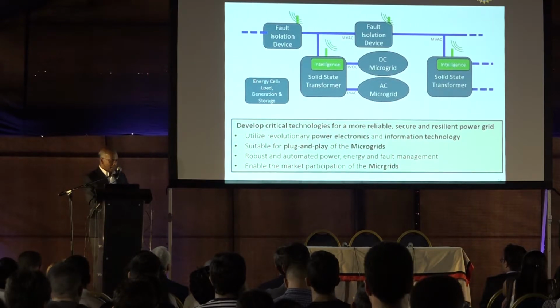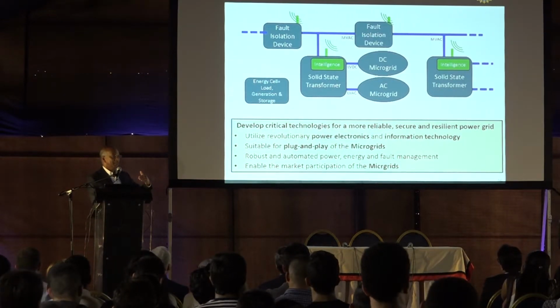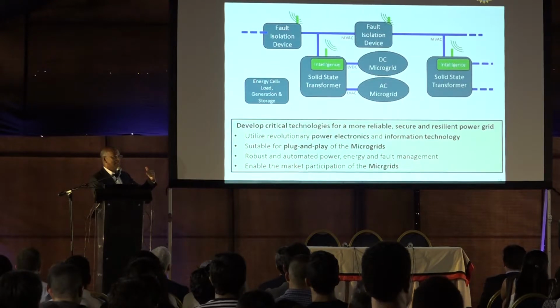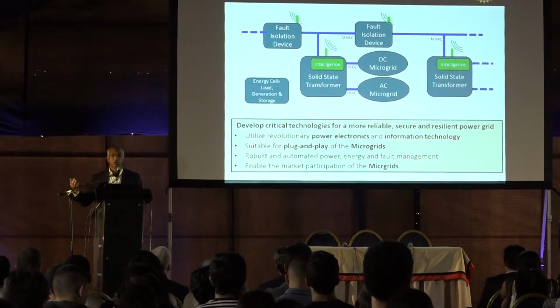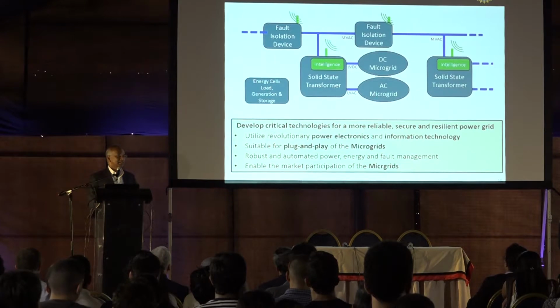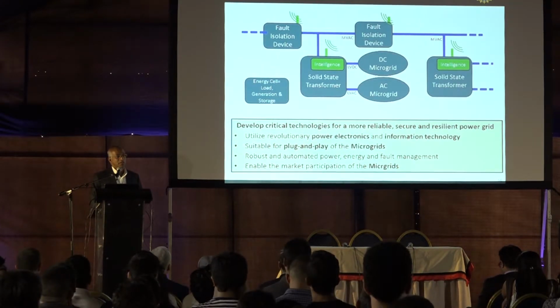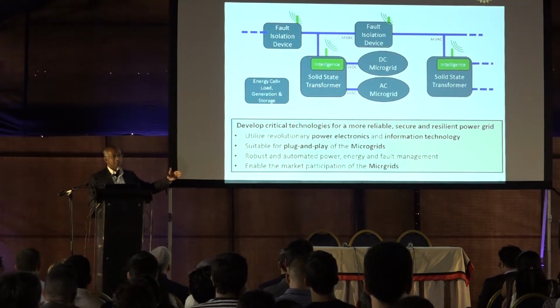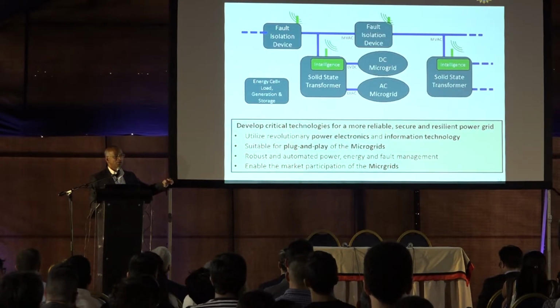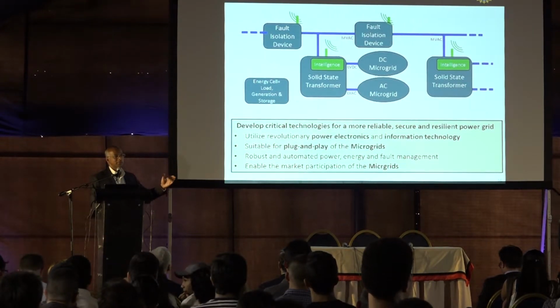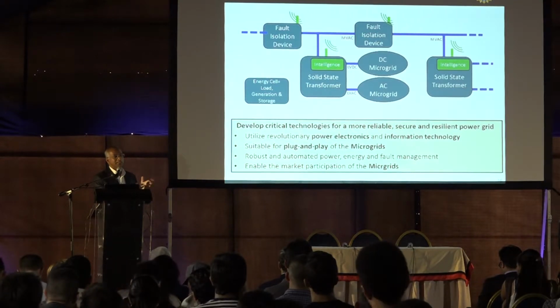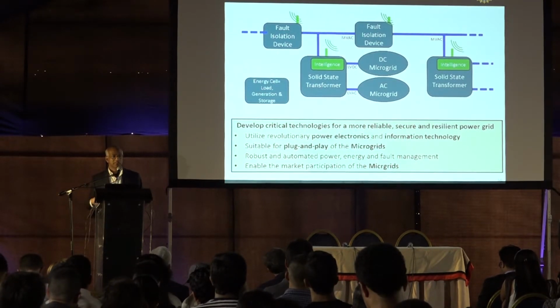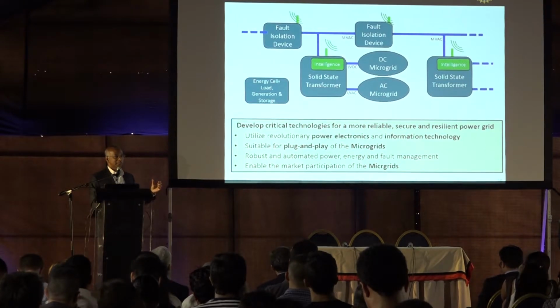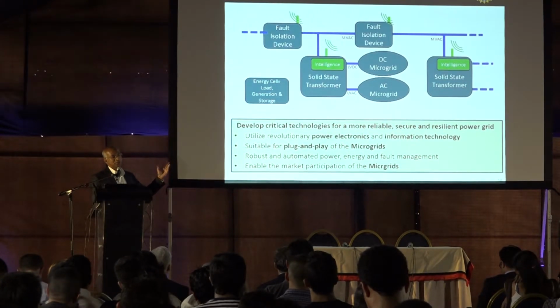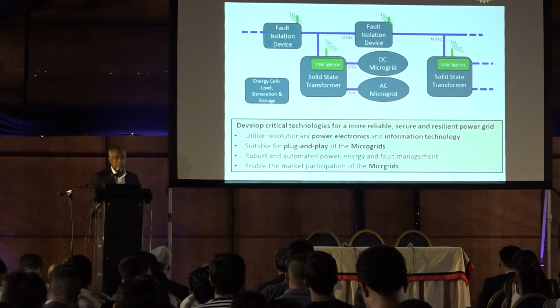If you think of the medium, we are on the distribution side, discussing the medium voltage level and lower. In our homes we get power supplies at 110 or 220 volts, but at the distribution transformer near our homes or commercial installations, power comes in at 480 volt AC, with variations depending on the region. There is a transformer that converts the medium voltage, 12 kV or 33 kV, into that low voltage—that's a distribution transformer.